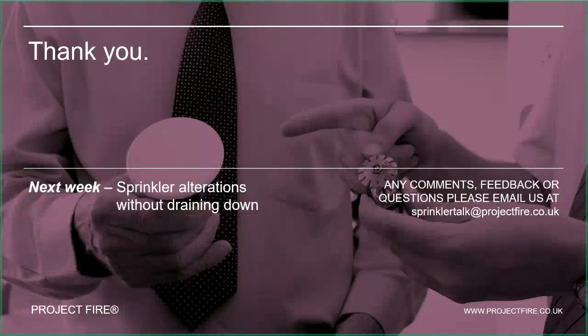So the alarm valve will trip and the water will go in. So we can't just crack on with a dry installation. But most commonly we're talking about a wet installation. We're going to have to get the water out of the pipes first, then we can drill in and make our alterations. But there is a way of doing this without draining down, and that's going to save a lot of time, a lot of water, and ultimately it saves money by saving time. So join me next week when I will talk about that.